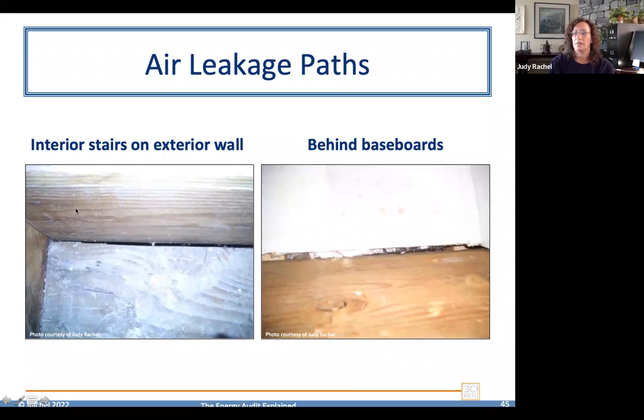Often if a house is carpeted, you will see dark impingement, dark stains at these seams, and we think as homeowners that I'm just not good at cleaning my house. But really, the dirt is actually impinged, and it's because of the pressure differences that are causing air leakage. So that dirt is actually a clue that it's an air leakage pathway.